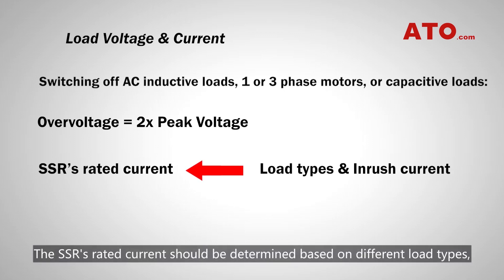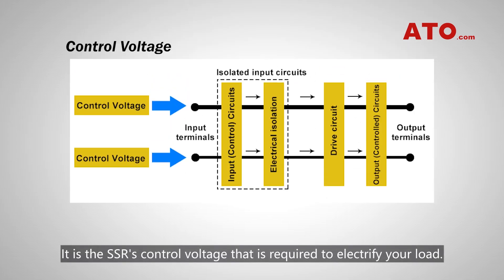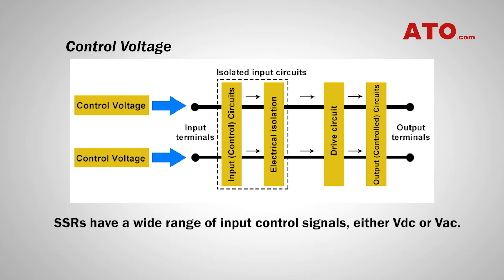The SSR's rated current should be determined based on different load types, depending on whether there is an in-rush current or not. Number 3: Determine the control voltage required to activate the SSR. It is the SSR's control voltage that is required to electrify your load. Unlike electromechanical relays, which are typically controlled by an unvaried voltage, solid-state relays have a wide range of input control signals, either VDC or VAC.